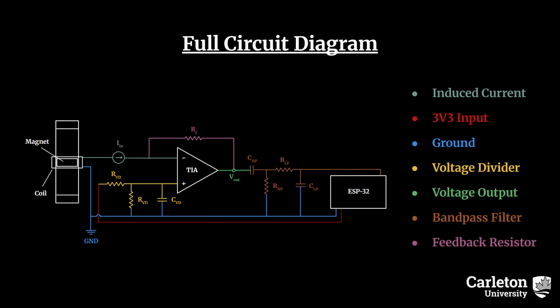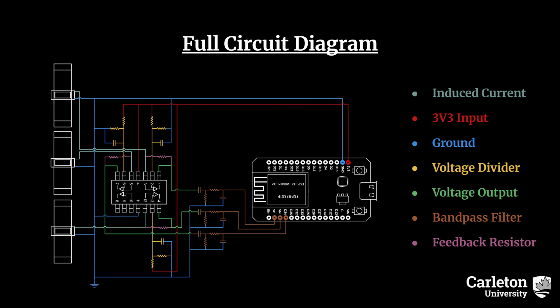As for the bandpass filter, it is there to attenuate high-frequency noise produced by electronics or extremely low-frequency non-dynamical vibrations produced by gravity field changes and/or instrument drift. With this information, the full circuit diagram of 3 axes can be drawn as such.